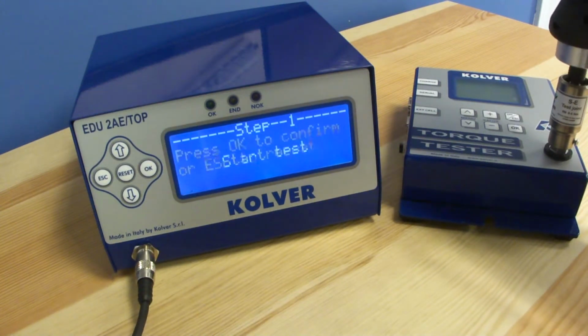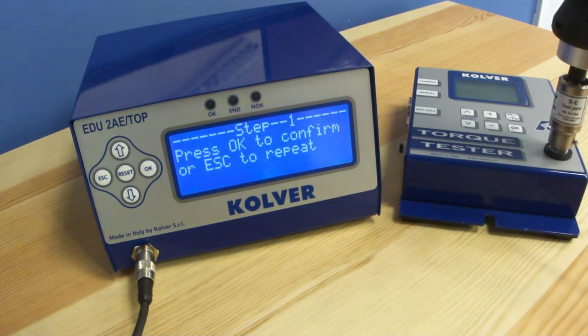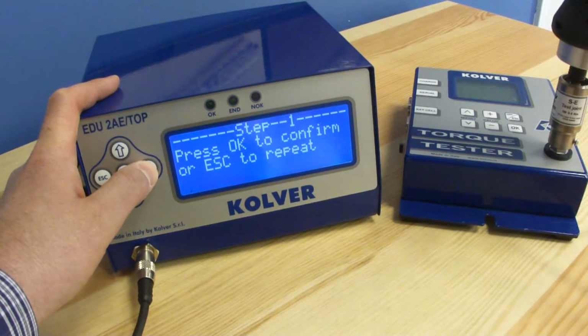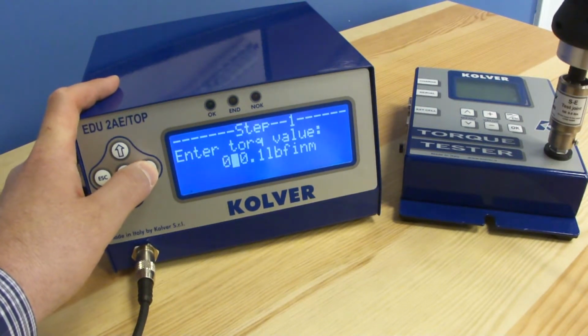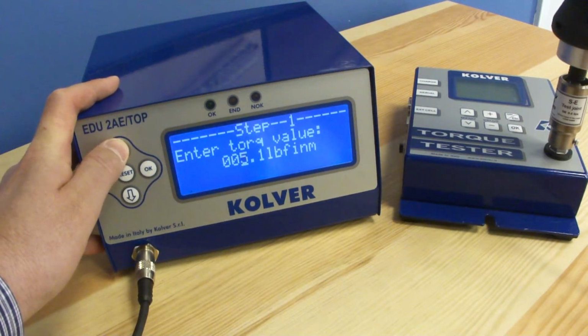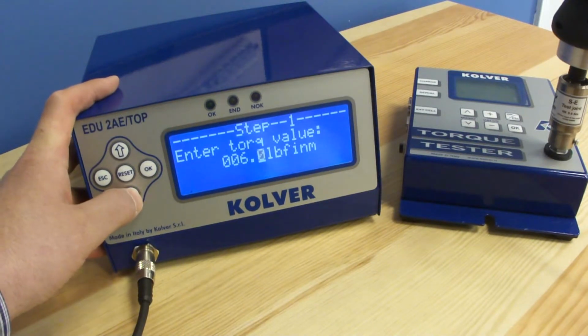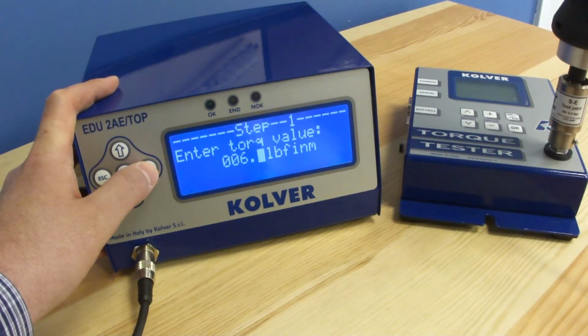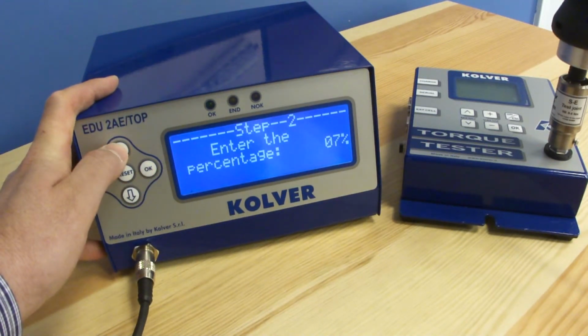By doing a series of rundowns, what I'm seeing is that my minimum of 5% reflects 6 inch-pounds on our calibrated torque tester. I recommend doing anywhere between 10 to 15 rundowns to take the average. This will give you the best results and the closest torque percentage. By hitting OK, we're now asked to move to step 2 and enter the percentage.